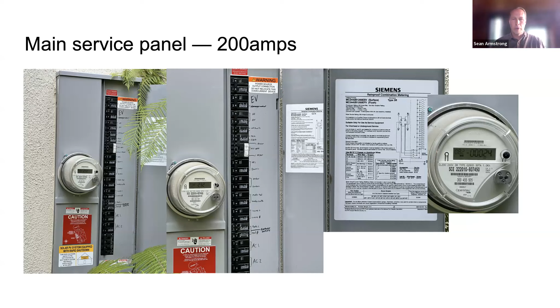This is what a 200 amp panel looks like, this is theirs. Tom did a terrific analysis of how you'd add more electric devices, because this box has a lot of black ink next to it, most of these circuit breakers are in use. There's plenty of space on the service, but this panel might need replacing, this metal box with metal connections, if you're not thoughtful about fitting smaller circuit breakers in. Just a little work here so you don't have to put in a new box, it's an expense you don't need if you can avoid it.